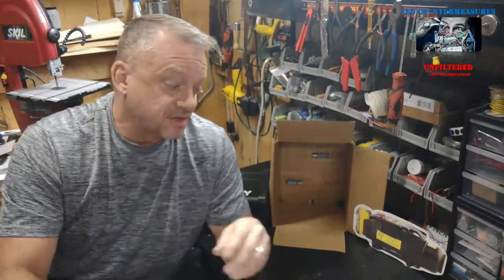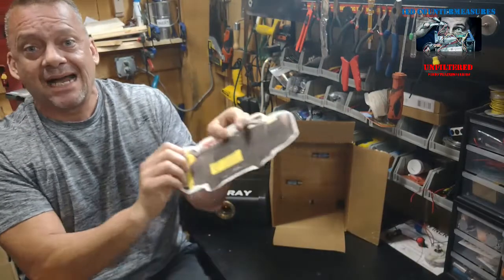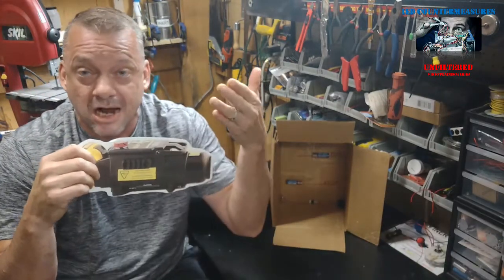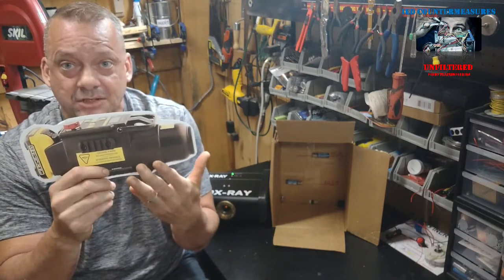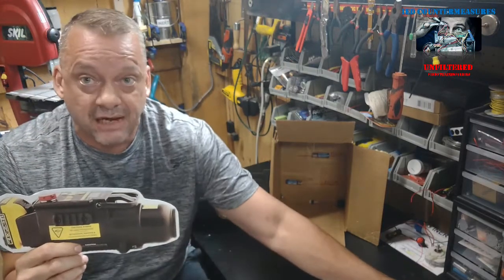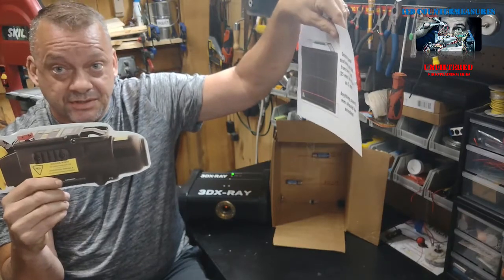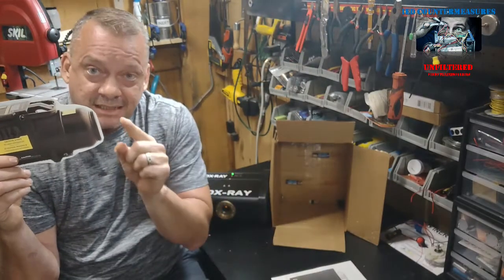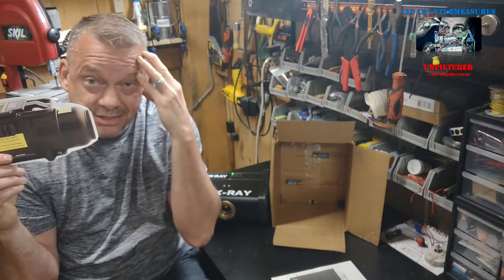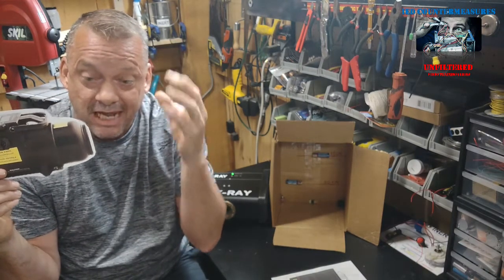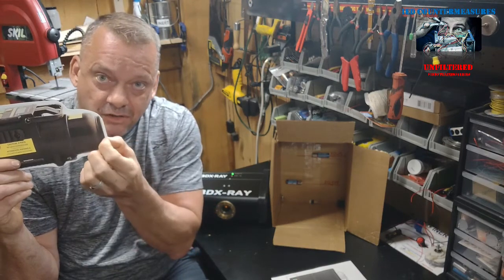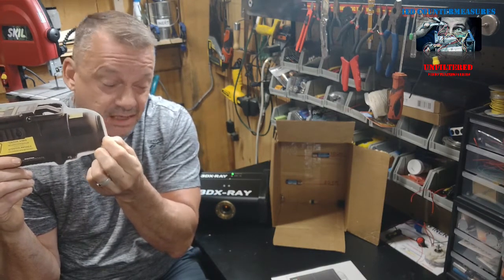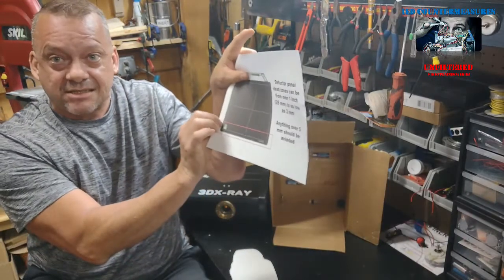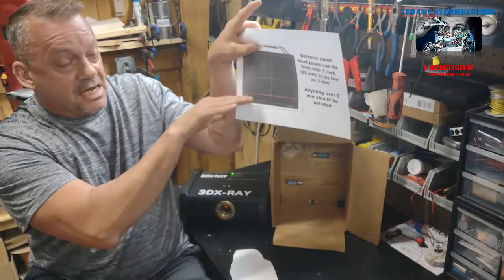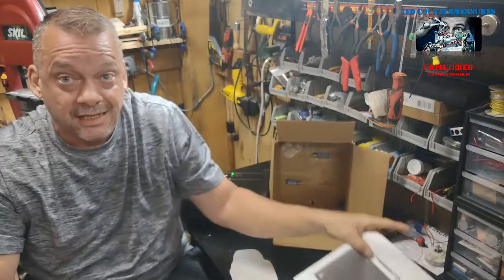There's another factor that you have to take a look at, and that happens to be the height of your generator off the ground, okay? So when you take something like the XR150 and you place it on the ground, and then you have your panel, okay, with it also sitting on the ground, it's basically a straight line, okay? This is the best way to look at this in your head. Draw a straight line from the lower part of the aperture where it produces the x-rays to the lower edge dead zone of your panel, okay? And anything that's underneath that line, okay, is not going to show up in your x-ray image.